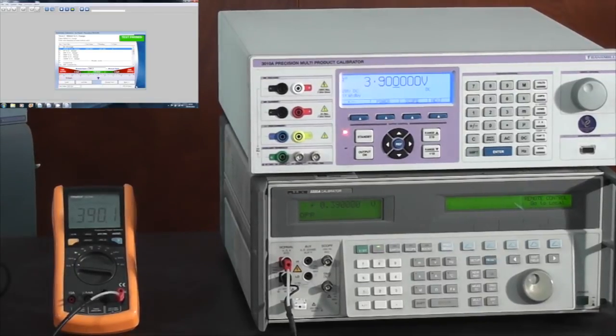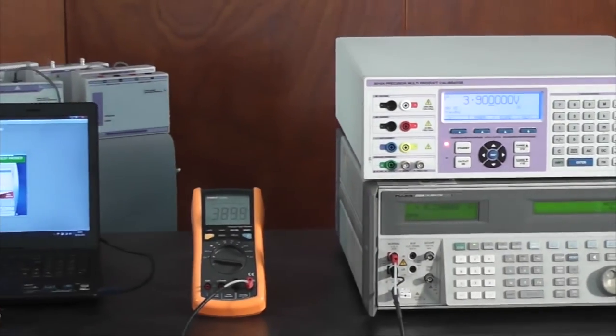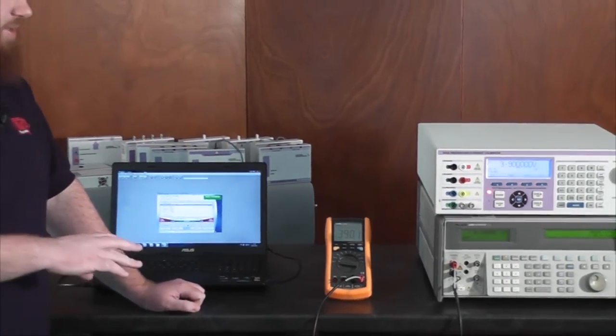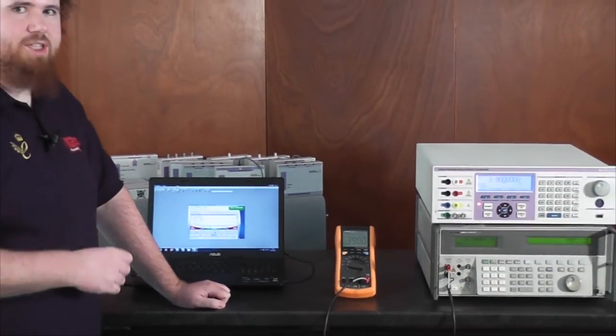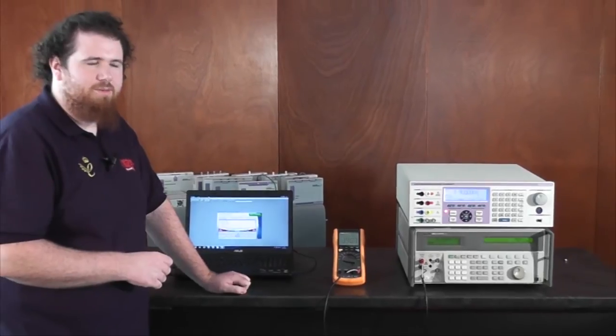As you can see in this short demonstration, I have not adjusted the procedure. I have simply changed the standard that ProCal is talking to.